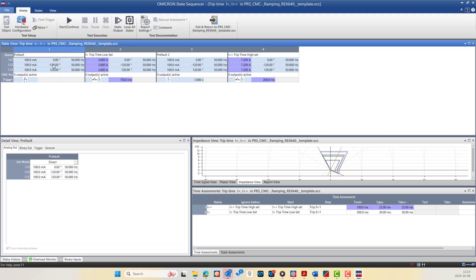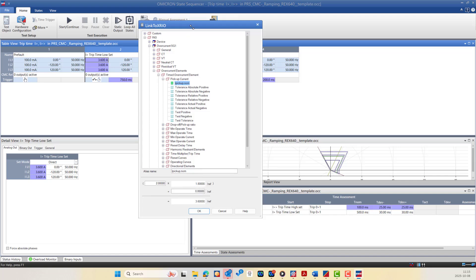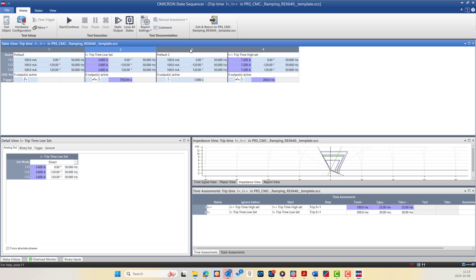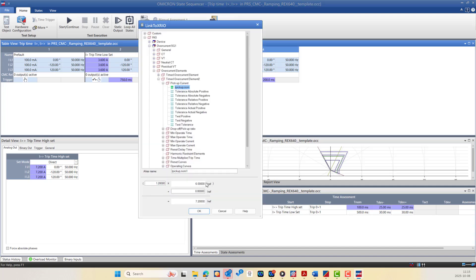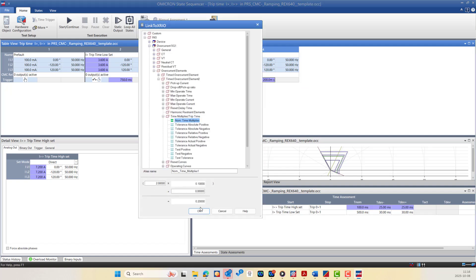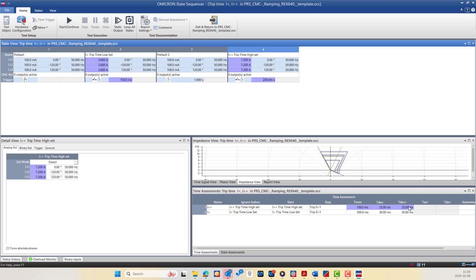Our test has four states: state one is the default pre-fault normal loading, state two is for I-greater (low-set over current, expected 500 ms), with the current value linked as a multiple of the nominal value — 1.8 A nominal multiplied by 2 equals 3.6 A. The time can also be linked and automatically adapted if relay parameter settings change, for example multiplied by 1.5 to equal 750 ms. For the I-double-greater high-set stage, the current is multiplied by 1.2 to equal 7.2 A and the expected trip time multiplied by 2 equals 200 ms. The Link to XRIO feature allows automatic adaptation to new relay parameter settings, including tolerances.